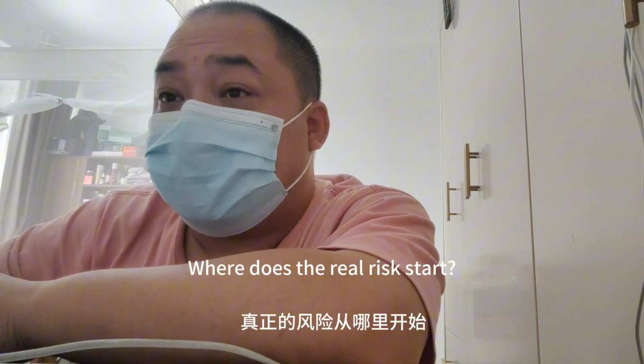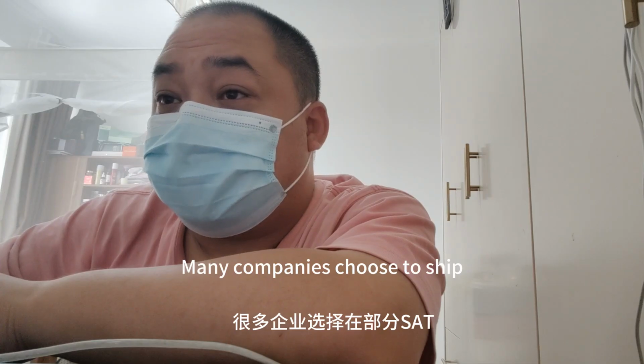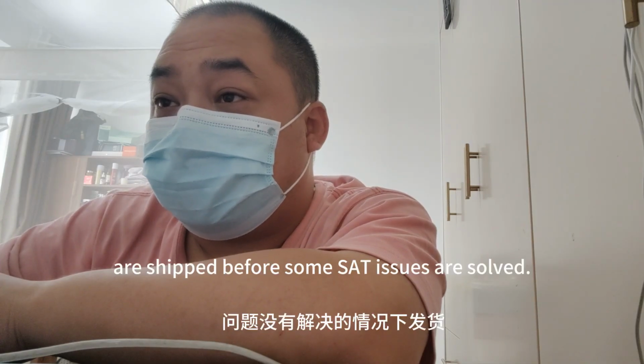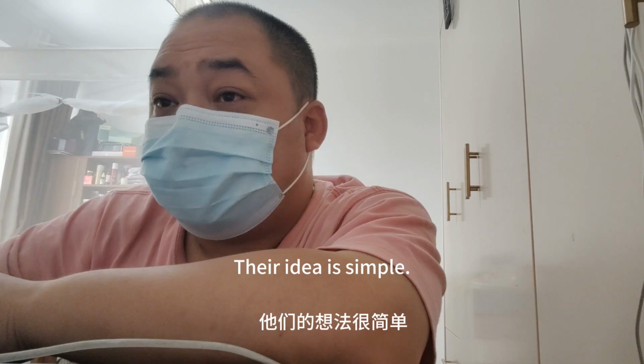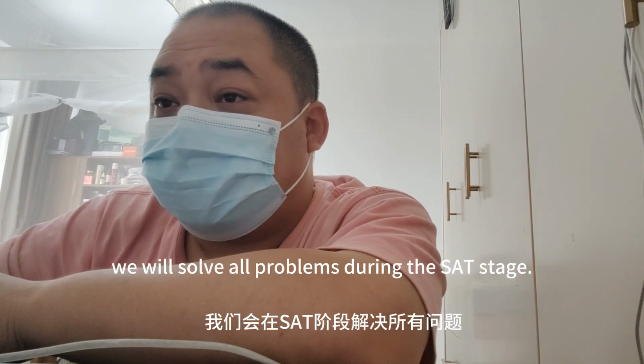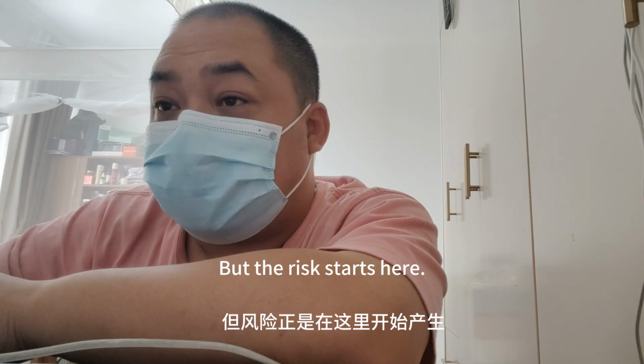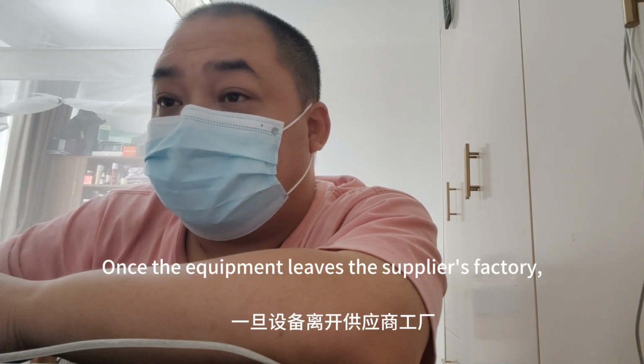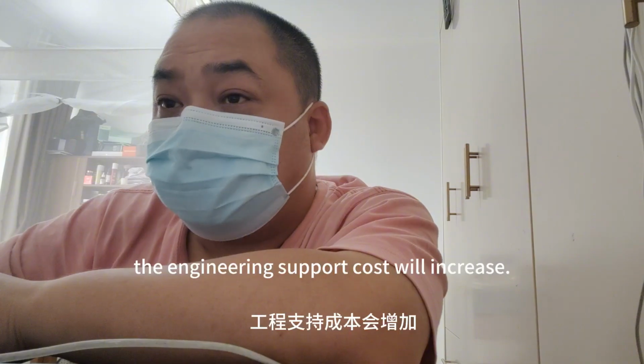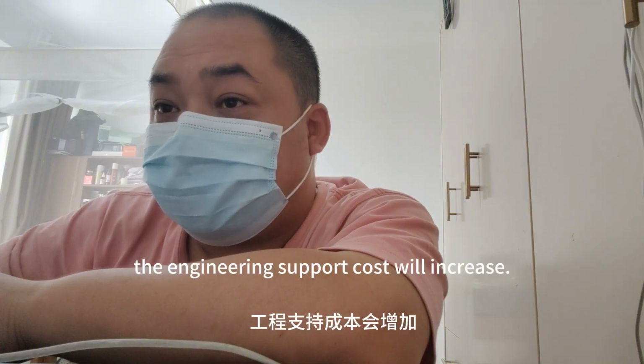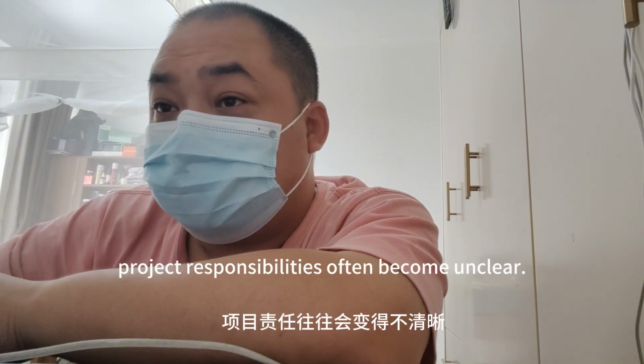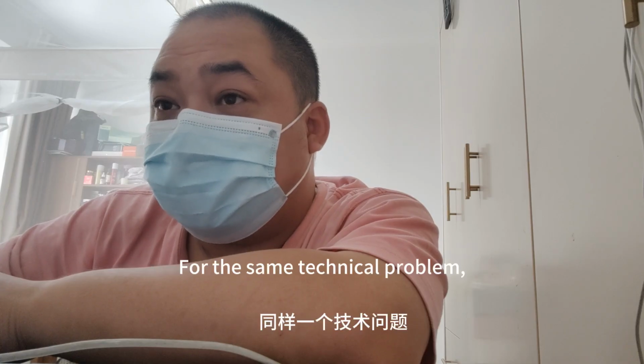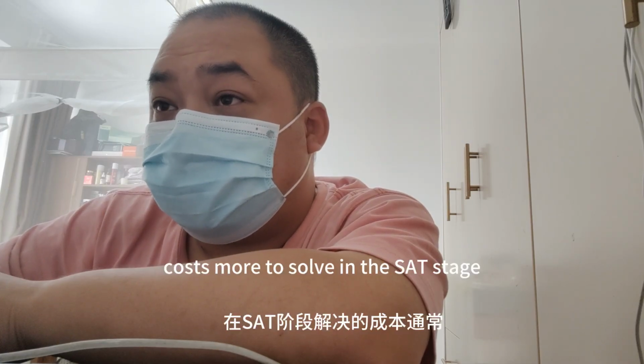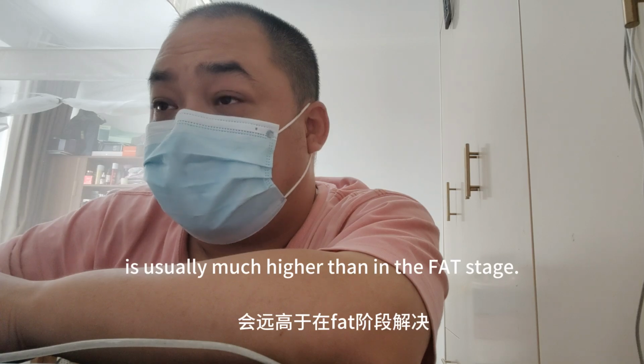Where does the real risk start? Many companies choose to ship the equipment before some issues are solved. Their idea is simple: we will solve all problems during the SAT stage. But the risk starts here. Once the equipment leaves the supplier's factory, the engineering support cost will increase. Communication efficiency will decrease. Project responsibilities often become unclear. For the same technical problem, the cost of solving it in the SAT stage is usually much higher than in the FAT stage.